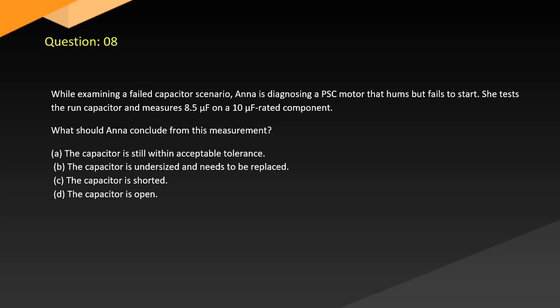Question 8. While examining a failed capacitor scenario, Anna is diagnosing a system that hums but fails to start. She tests the run capacitor and measures 8.5 µF on a 10 µF rated component. What should Anna conclude from this measurement? A. The capacitor is still within acceptable tolerance. B. The capacitor is undersized and needs to be replaced. C. The capacitor is shorted. D. The capacitor is open.